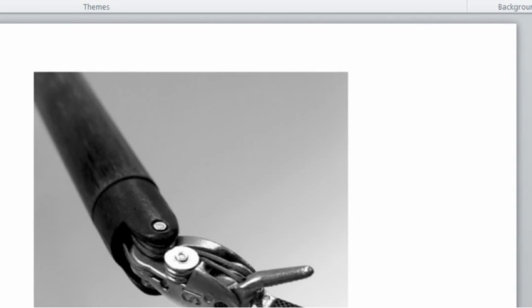The placement of the sensing elements is also an important factor that could greatly influence the quality of force measurement. Basically, there are at least four locations where the sensing elements might be placed. These show the four possible positions to place sensing elements. Number one is located near the actuation mechanism driving a joint. If a surgical instrument has an active joint driven by some source of actuation, it is possible to measure force acting at the instrument tip by monitoring the stress of the mechanical linkage or the response of the actuator.